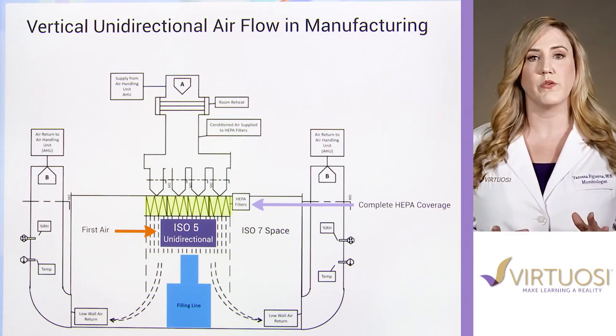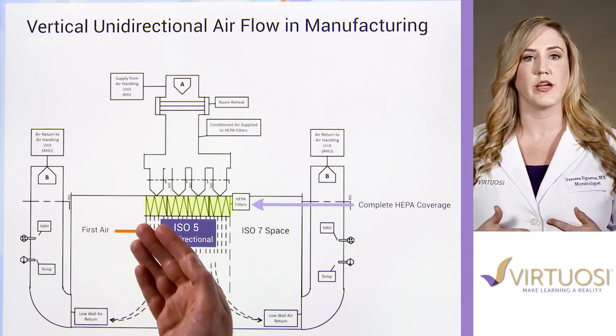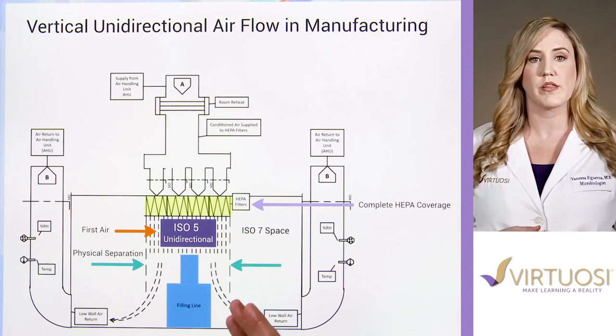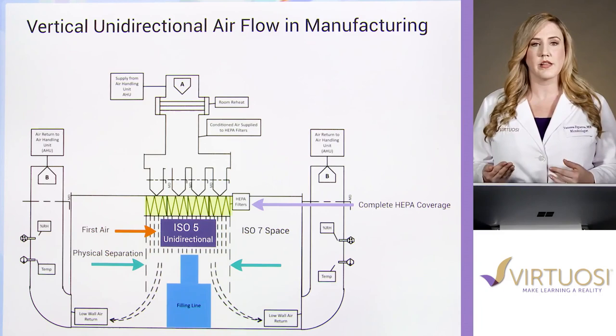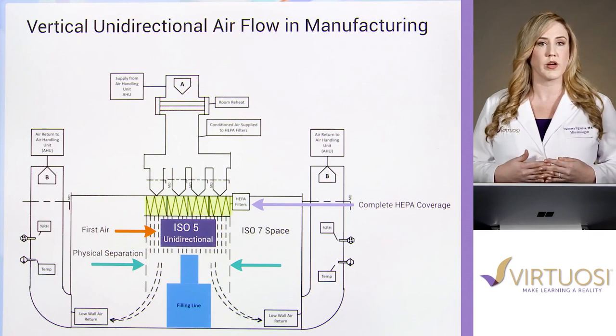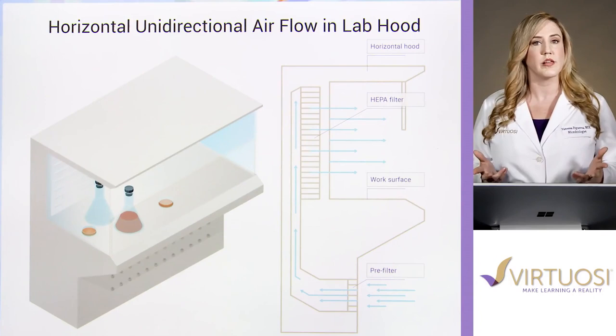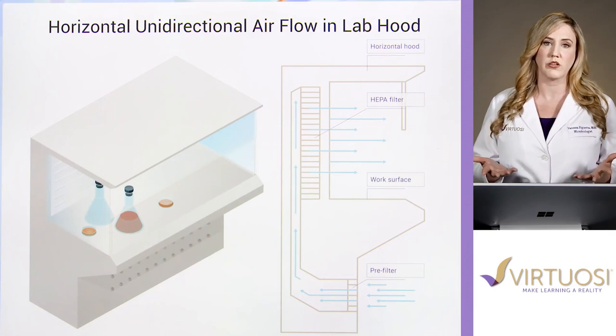Maintaining first air minimizes the potential for contamination and ultimately protects the product and therefore patient health. Unidirectional airflow is created by complete coverage of the supply area with HEPA filters. The air under the ISO 5 space is physically separated from the ISO 7 space via rigid plastic walls known as RABS, or restricted access barrier system. The air passes over the filling line, exits the space, and is captured by the low wall returns. Unidirectional airflow is also referred to as laminar airflow, and standalone equipment are called laminar airflow hoods, abbreviated as LAF.